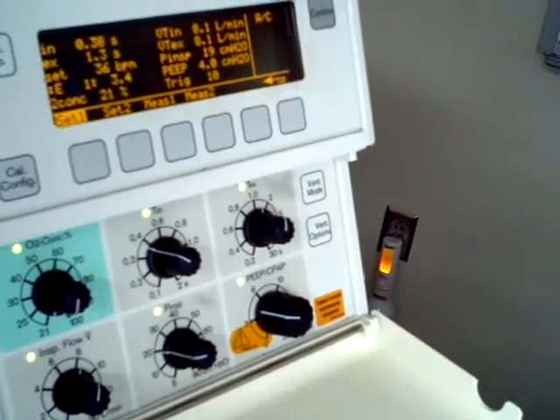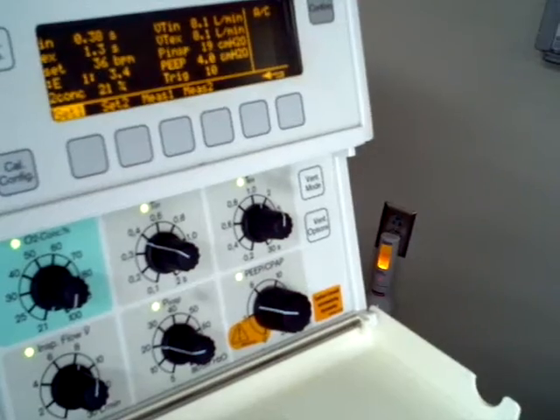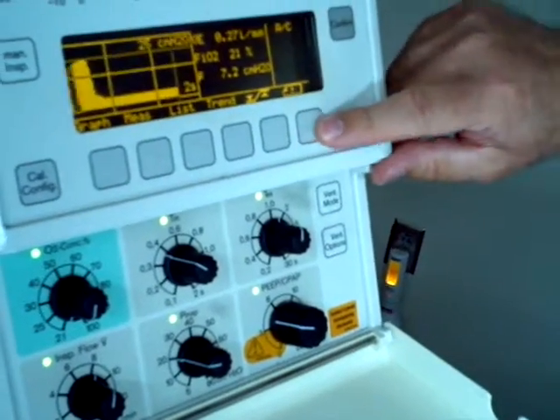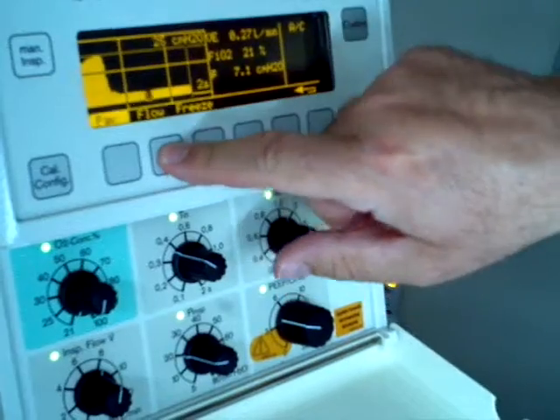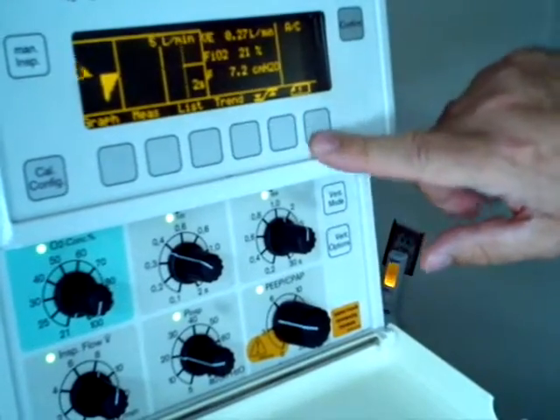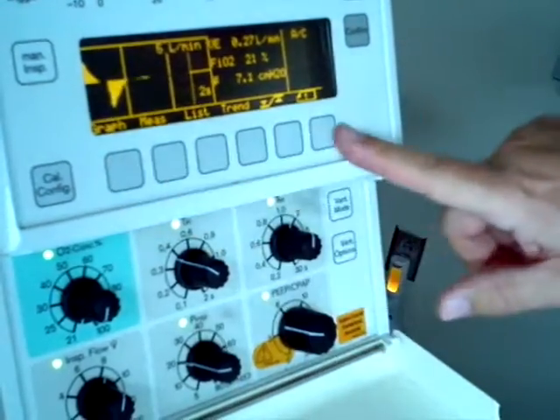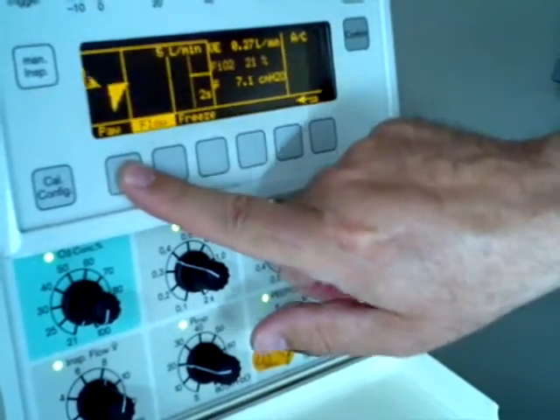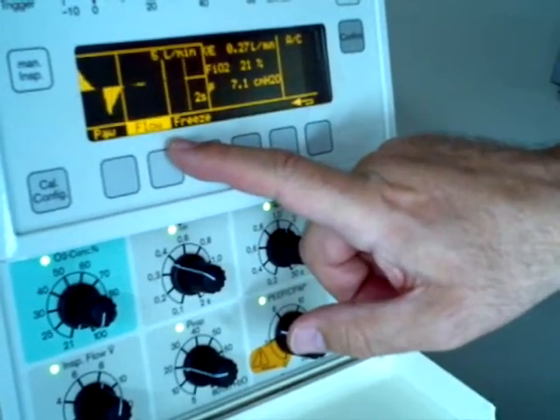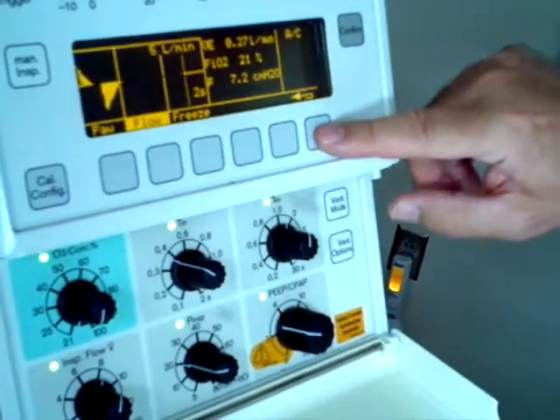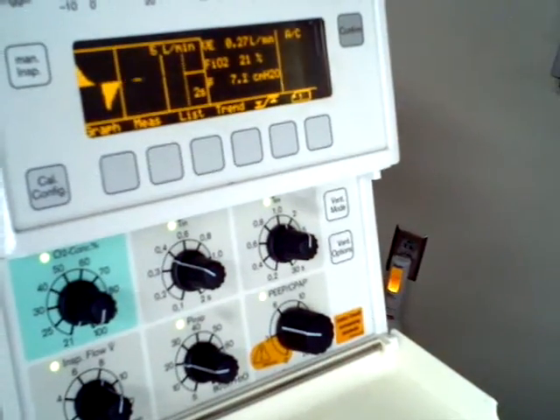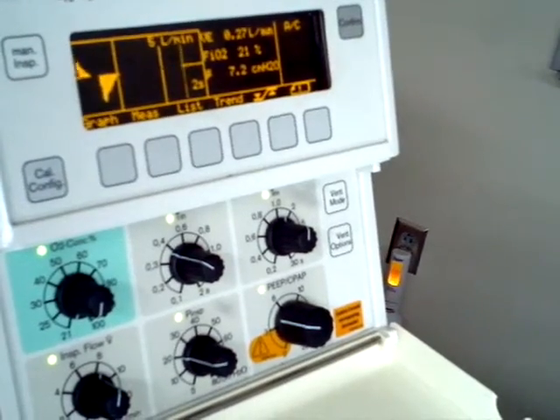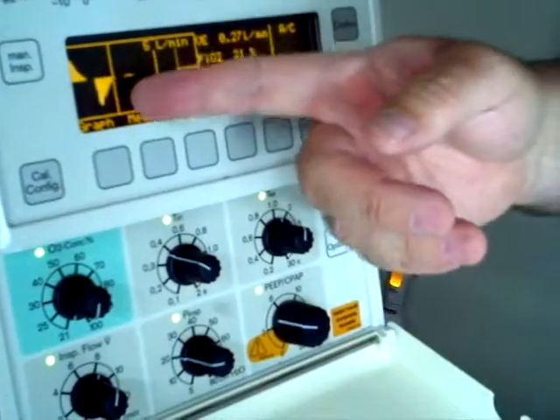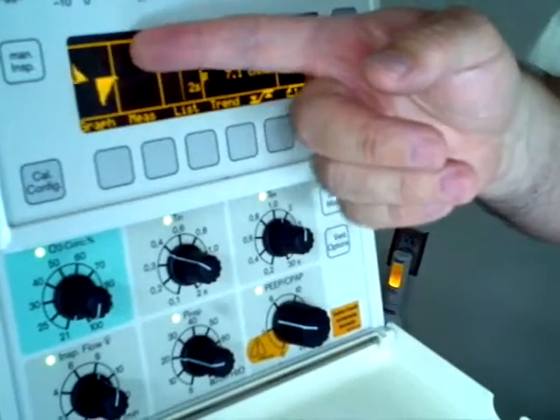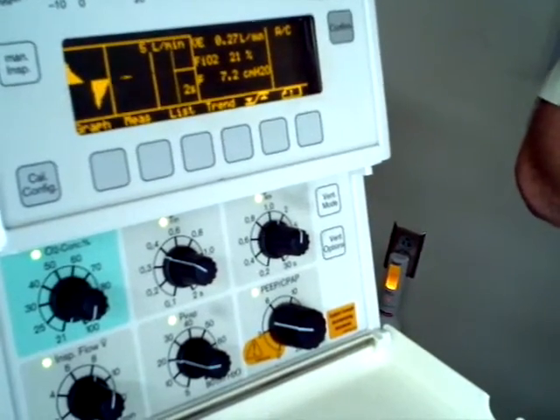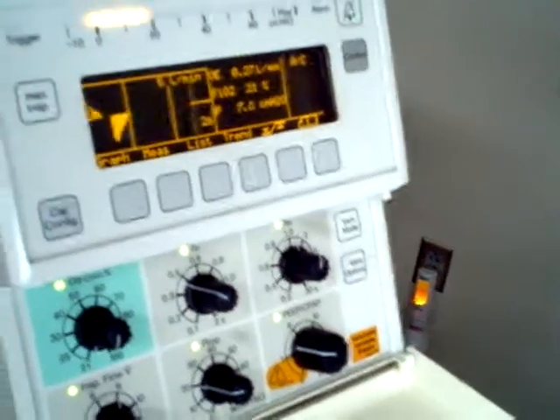Okay. What else? This is going to be a little tricky, so what I would do is switch to a flow curve. Let me go back and show you how to do that. So if you go to graph, this is our home screen, right? I go to graph, my choices are pressure or flow, right? I would select a flow curve, and I would set my inspiratory time first. And when I set my inspiratory time, I prefer to not have a lot of pause time there, or much of a gap between my inspiratory flow and my expiratory flow. So how would I get rid of that gap?